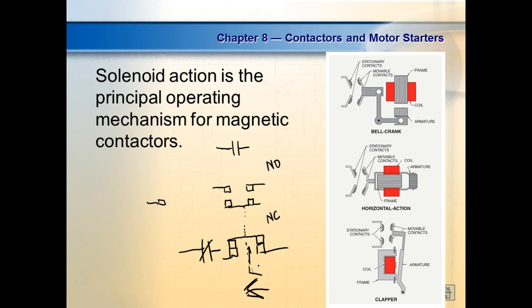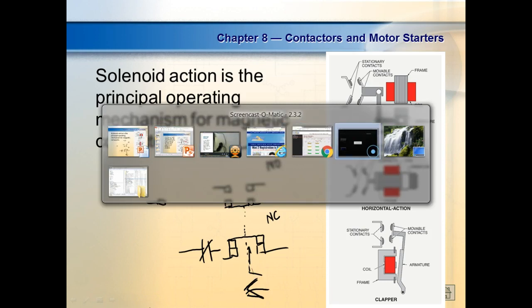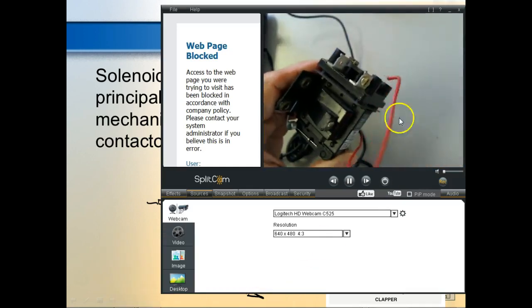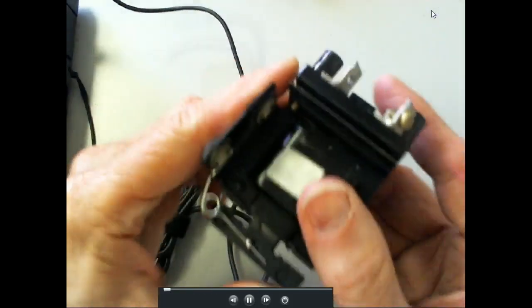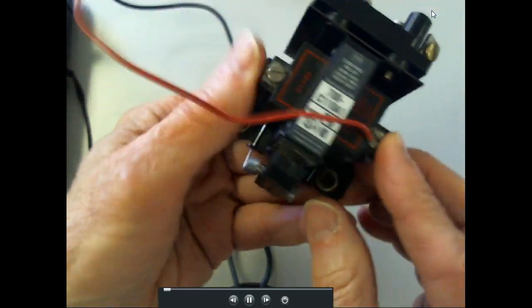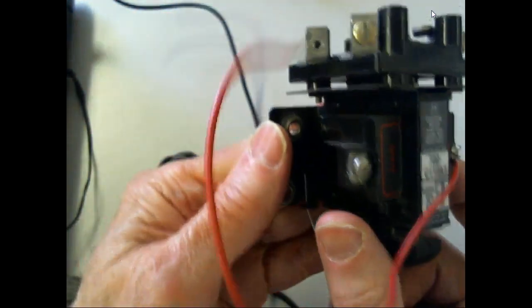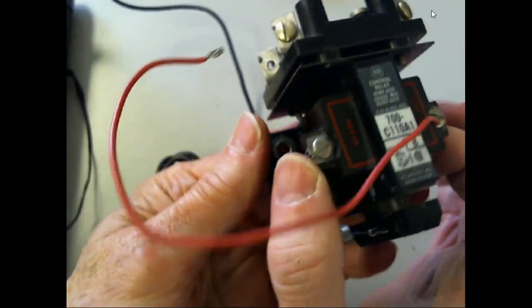Normally, in industrial relays, you can't see the solenoid coil because of the wire. I think I showed you magnetic wire. It has really, really thin insulation, trying to get a real good coupling between the conductors. So if anything scratches them, it could literally create a short, right? So what they do is encapsulate the solenoid coil itself in plastic in industrial relays. So here's the solenoid coil.